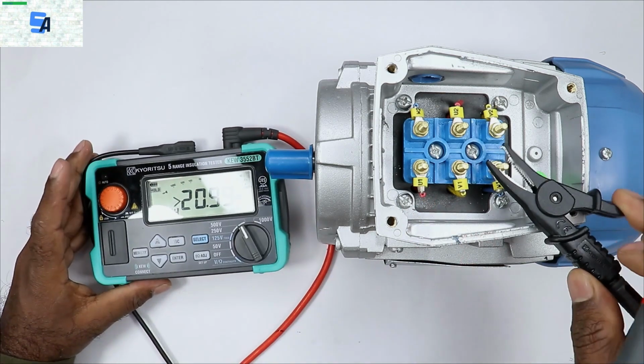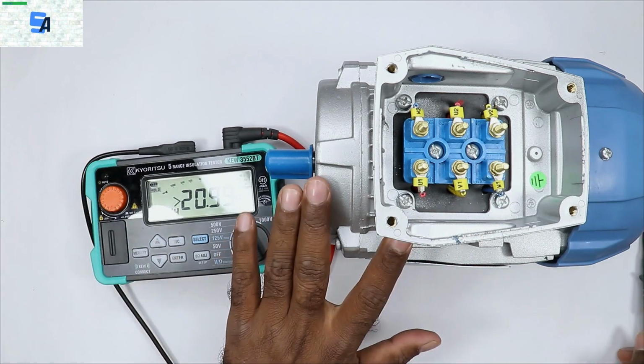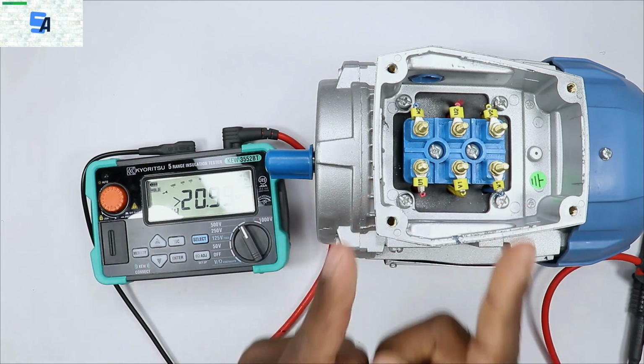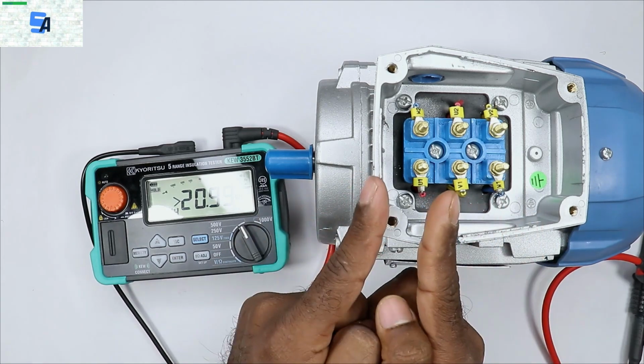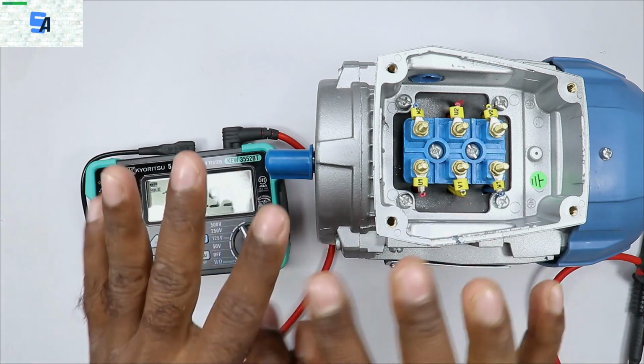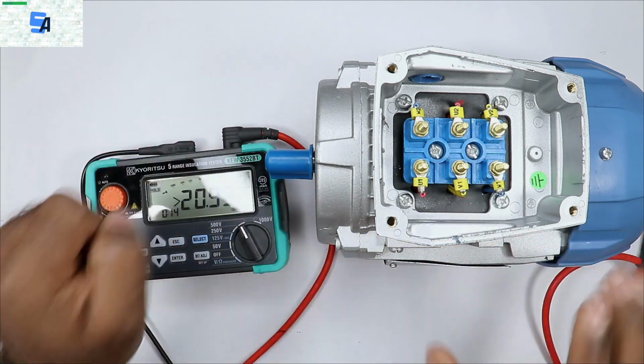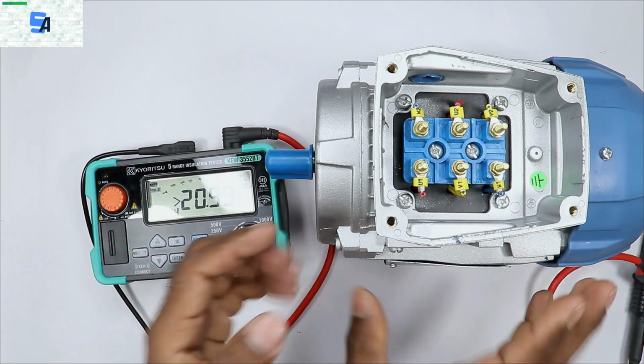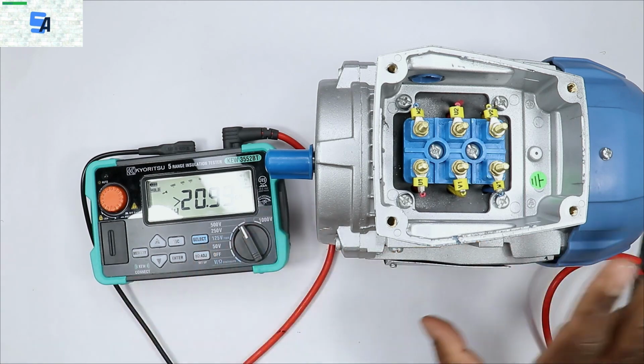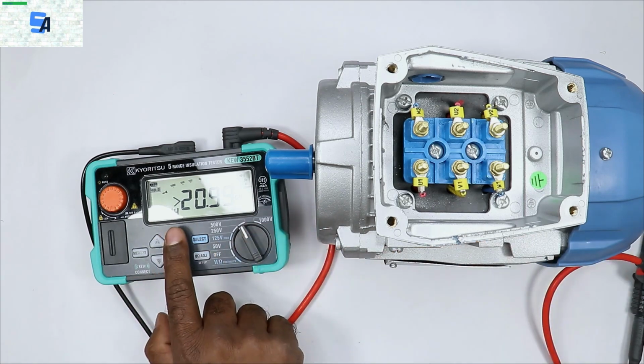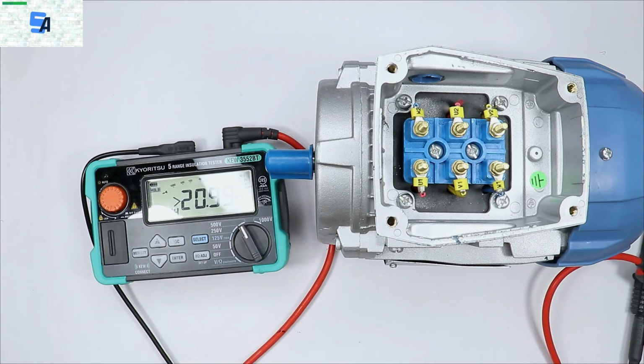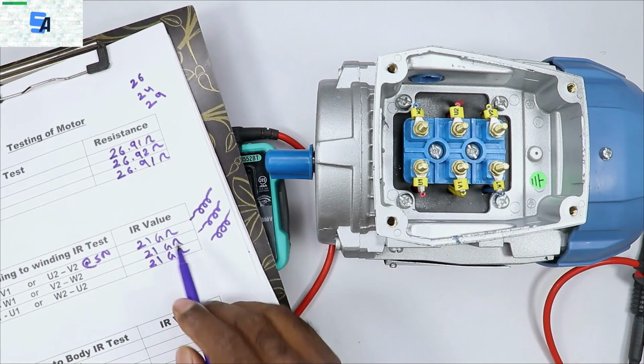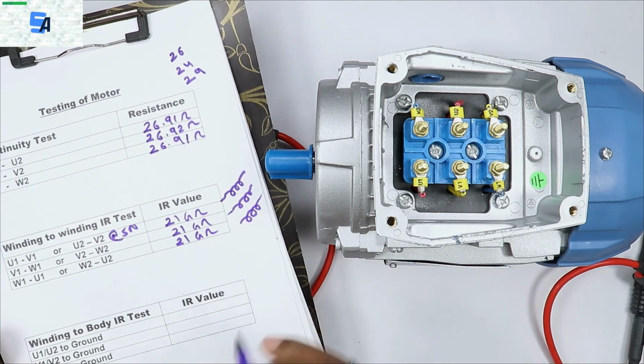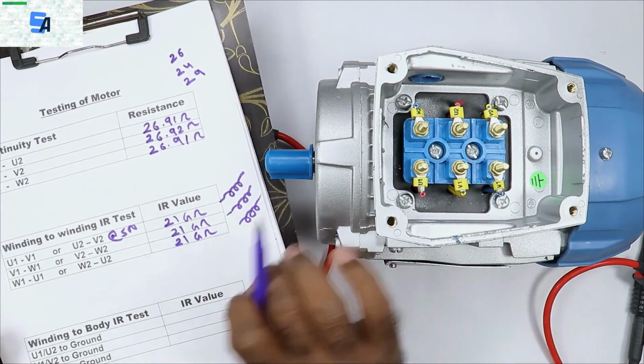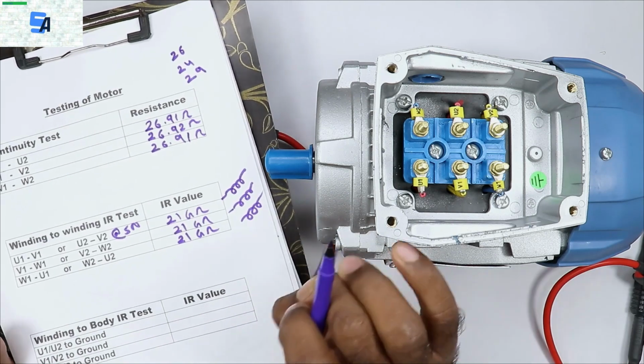It means for now we can say that the gap between all 3 windings of the motor, or we can say the insulation of the windings, is absolutely okay. The motor which I am using here is completely new. This is why we are getting a proper IR value. If you measure the IR value of a used motor, you will get less IR value than this. Now I will tell you at how much IR value we can say there is some problem in the motor.